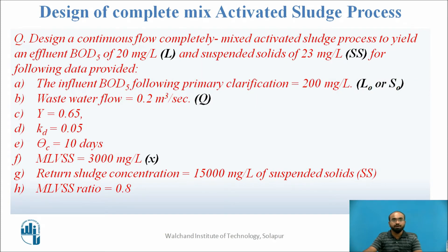This is the typical question we are working on, and we had completed five steps. The question is: design a continuous flow complete mix activated sludge process to yield an effluent BOD of 20 mg/L and suspended solids of 23 mg/L. Influent BOD (S0) = 200 mg/L, wastewater flow rate Q = 0.2 m³/s, Y = 0.65, KD = 0.05, theta_C = 10 days, MLVSS (x) = 3000 mg/L, return sludge concentration = 15,000 mg/L SS, and MLVSS ratio = 0.8.